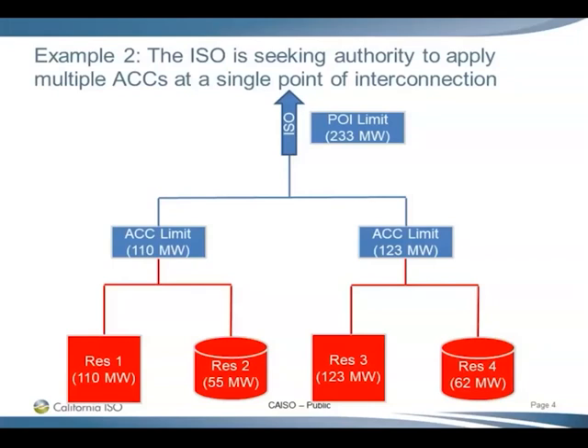In this case, there could be an aggregate capability constraint applied to resource 1 and resource 2 at the 110 megawatt limit, and a second aggregate capability constraint applied to resource 3 and resource 4 at the 123 megawatt limit. These two aggregate capability constraints would align with the studied point of interconnection limit of 233 megawatts that the ISO has studied and reviewed for the overall point of interconnection limit for injecting energy into the ISO.